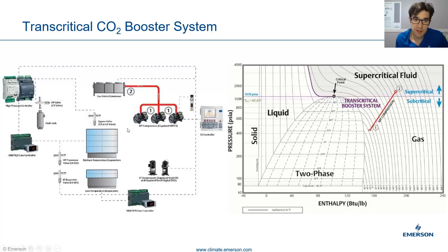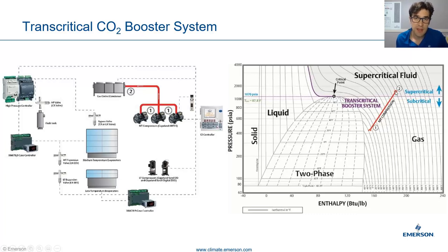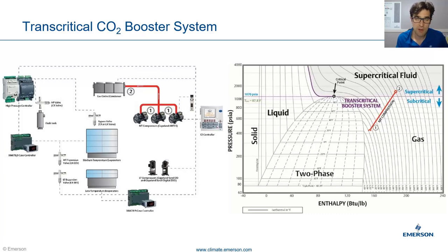So the first thing you see here is the MT compressors, one to two — this is your heat of compression from your compressor, as you can see over here, one to two on our enthalpy diagram. And now we're up, and as you can see, in the supercritical fluid zone or our transcritical zone, any time we're above 87.8°F or 31°C, we are in our transcritical zone.